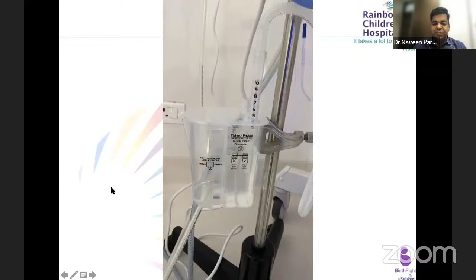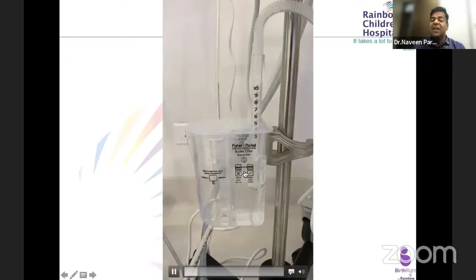Now look at this. The bubbling is too much. It is continuous bubbling. It is so much that it is raising the water column. Why? Because somebody has inadvertently increased the flow rate. So CPAP being delivered is maybe higher than the set CPAP. So the action needed is to decrease the flow rate.